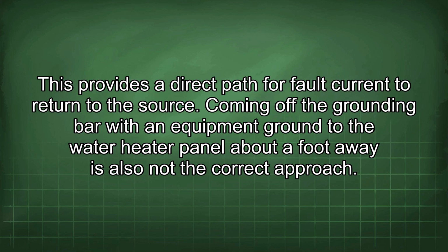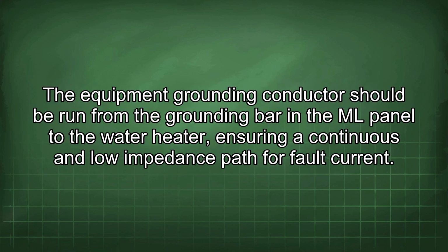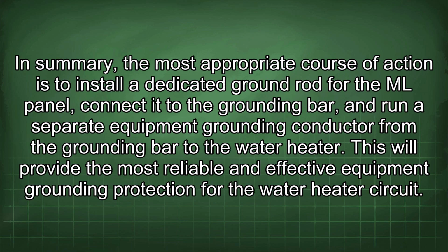Coming off the grounding bar with an equipment ground to the water heater panel about a foot away is also not the correct approach. The equipment grounding conductor should be run from the grounding bar in the ML panel to the water heater, ensuring a continuous and low impedance path for fault current. In summary, the most appropriate course of action is to install a dedicated ground rod for the ML panel, connect it to the grounding bar, and run a separate equipment grounding conductor from the grounding bar to the water heater. This will provide the most reliable and effective equipment grounding protection for the water heater circuit.